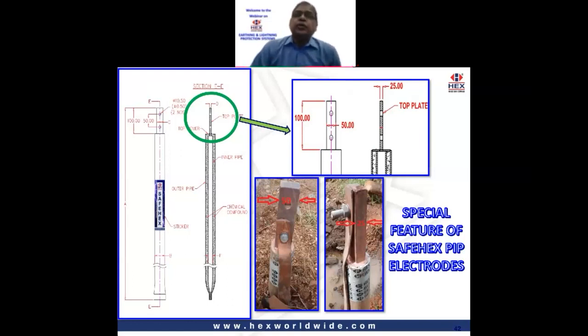Now, the other feature is what I already told you in the previous slide, which is that they are hot dip galvanized after fabrication. But whether they are hot dip galvanized or copper plated in our own plant, both the inner primary electrode and the outer secondary electrode are plated to the thickness ordered by our customers. So if you want 100 microns, we will give you both the inner and outer electrodes in 100 microns. If you want 250 microns, both the inner and outer electrodes are 250 microns, which, sad to say, many people are not doing.